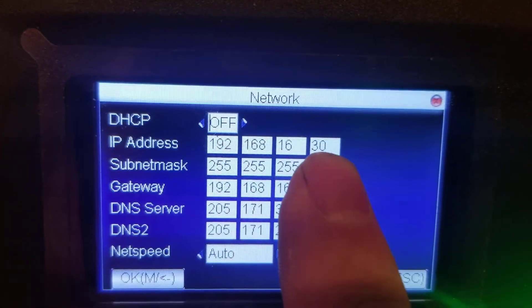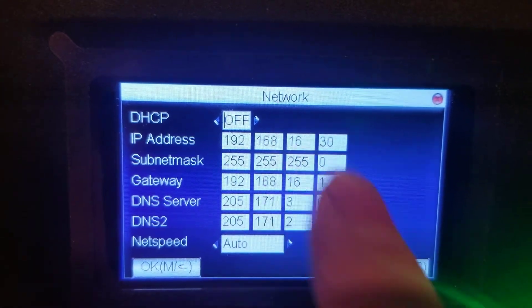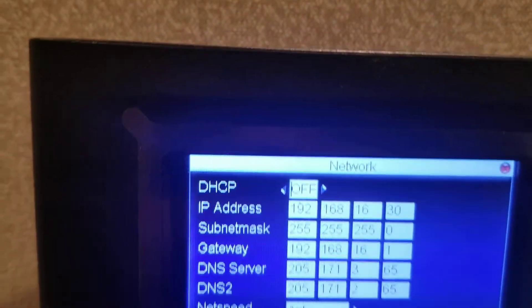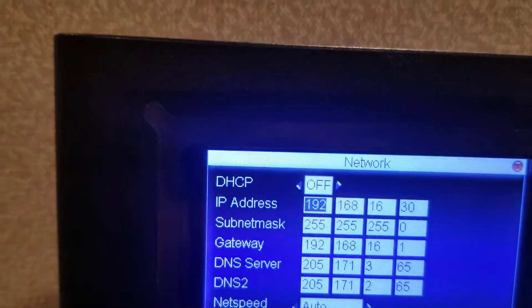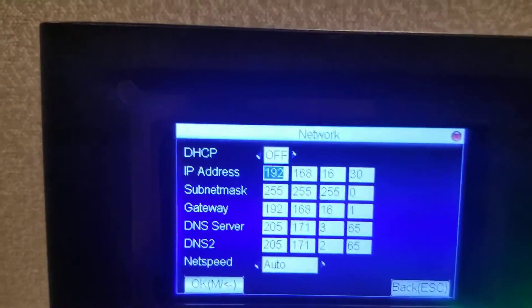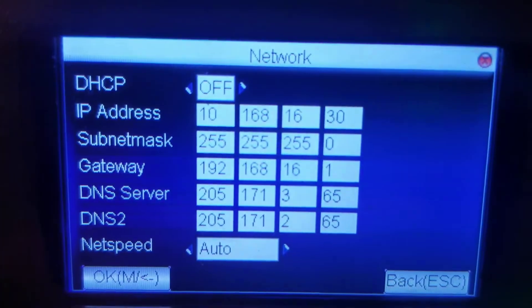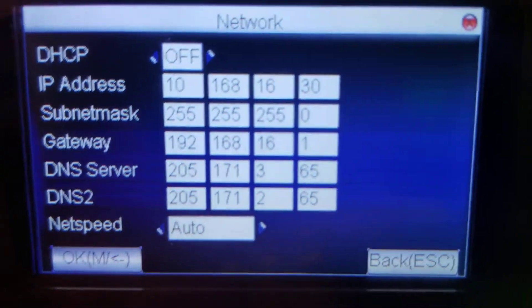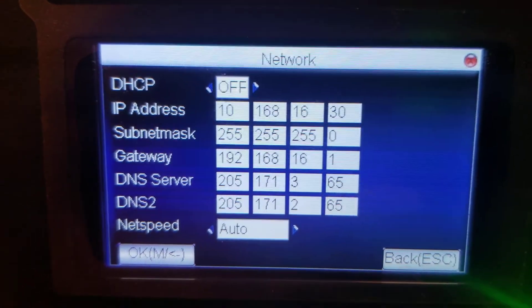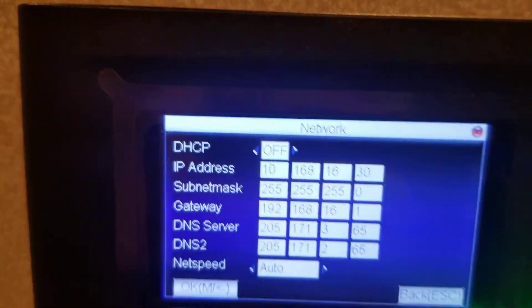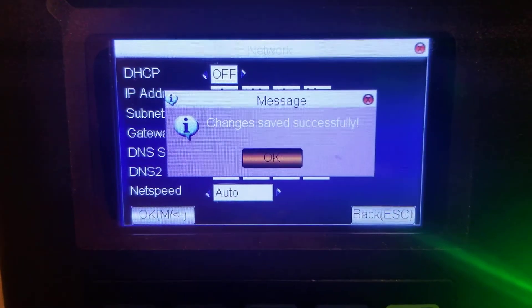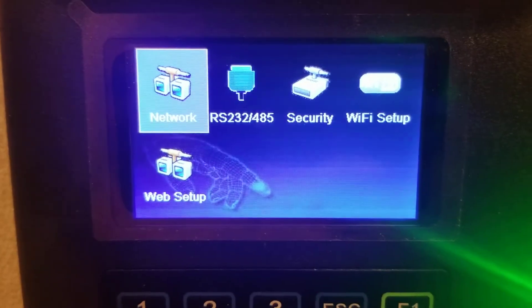The main thing we want to make sure is that it did not grab an IP address that the Wi-Fi could potentially use. So I press my down arrow and change this to a 10 — that's not part of my network, so that's all good. I press the Enter button, and we see 'Changes saved successfully.' I press Enter again to exit this screen.